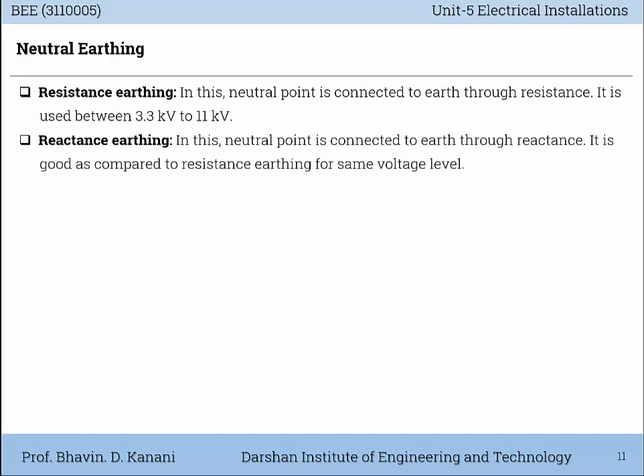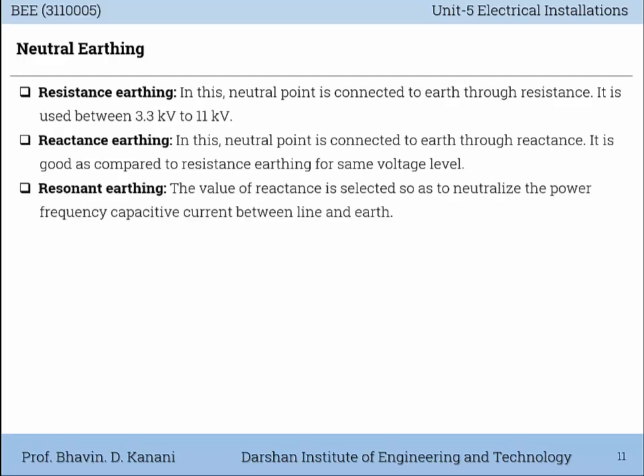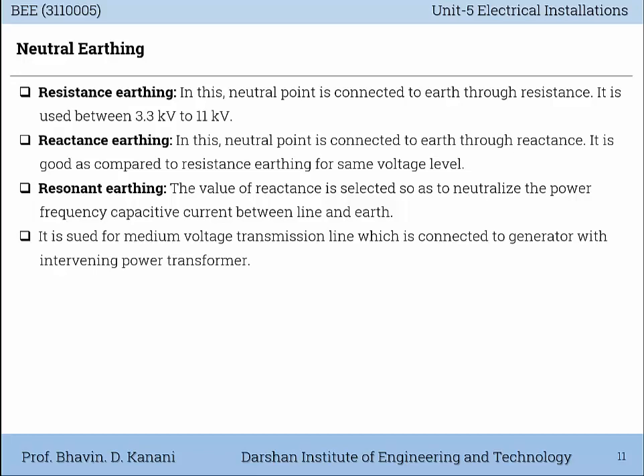Reactance earthing. In this method, the neutral point is connected to the earth through reactance. It is as good as resistance earthing for the same voltage level. Resonant earthing. The value of reactance is selected so as to neutralize the power frequency capacitive current between line and earth. It is used for medium voltage transmission lines which are connected to a generator with an intervening power transformer.